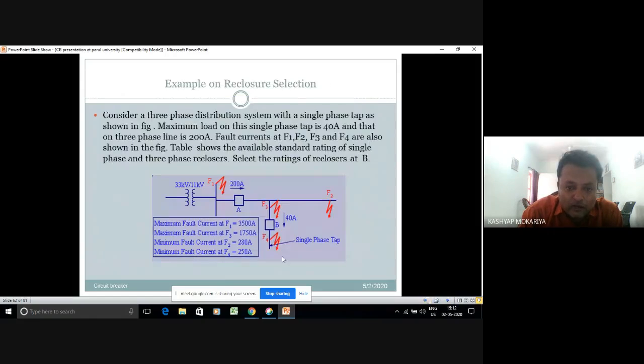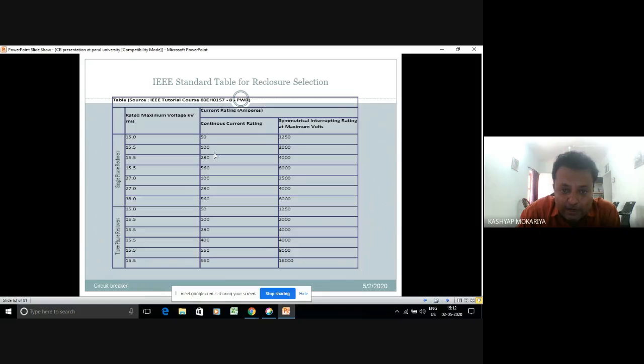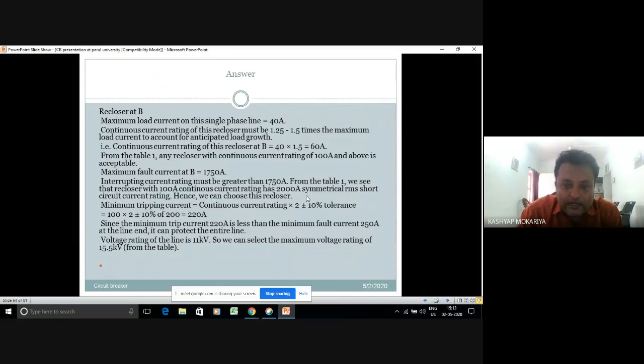Now the next thing is the maximum fault current at B. We have to go back again to the figure. At B the maximum fault current, say at F3, is 1750 ampere. So again you have to come back to the table. Just as you got the continuous current rating, you will get the symmetrical interrupting rating at the maximum voltage. Say it is 2000 ampere. So the 2000 symmetrical ampere current we have chosen.